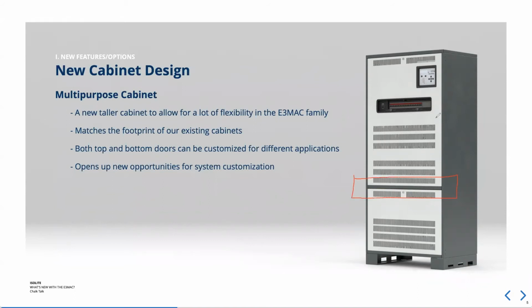This can have a big door up top and a small door on the bottom, or it can be swapped so you get a small door on top and a big door on bottom. We also have the flexibility to make this a totally blank face, so it could just be a large battery enclosure, or add breaker holes to make it an additional breaker section, or any combination of those. It has the same footprint as our existing large cabinets, just taller, which gives us a lot of flexibility.